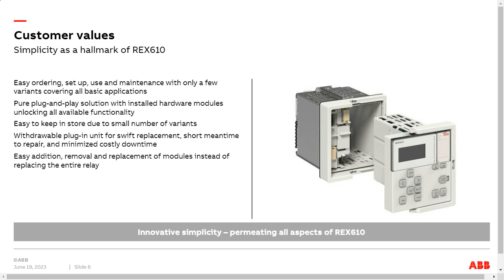Okay, a withdrawable plug-in unit for swift replacement. If there is a problem, basically you can take the plug-in unit of a REX610 and replace the one having an issue. So it's easy to add, remove and replace modules instead of replacing the entire relay. Of course this improves the mean time to repair.